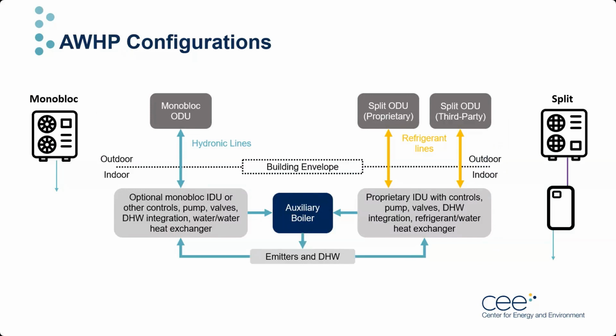And there's a lot going on here, so let's start at the outdoor unit for each of these and then move downwards. Starting at the monoblock ODU on the top left, we see that the hydronic loop in blue is what crosses the building envelope with the dashed line, going downwards from the outdoors to the indoors. Once indoors, there is no additional heat exchanger, but there may be an optional indoor unit that packages controls and other system components together for ease of install. There is then an inline auxiliary electric boiler that serves as a backup heating system that can supplement the heating provided by the heat pump if needed.